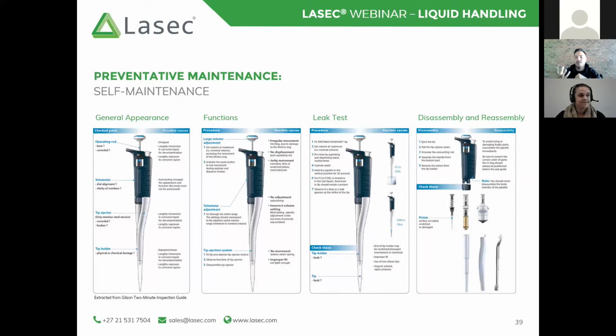So because we calibrate a pipette as a system, as a unit, we are accounting for any possible defects in that tip holder, for example, any defects in that piston assembly. And by accounting for those, we've now calibrated that system. It's now working as it was calibrated.